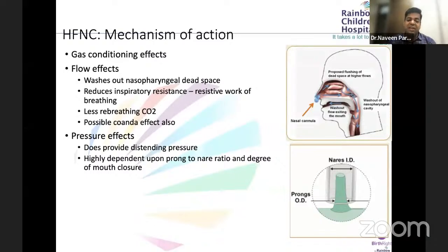The pressure effect does provide distending pressure, highly dependent on the prong to nare ratio and the degree of mouth closure. Always remember one thing. In CPAP, I was emphasizing more and more that if you are using short binasal prongs, there should be no leak. So that means they should fit the internal nare snugly. In CPAP, there should be no leak. In high flow, the diameter of the high flow nasal prong should be 50% of the nare diameter. So there should always be a leak, because if there is no leak in high flow and the baby closes the mouth, the whole of the flow will go inside the lung and the lungs will blow out.